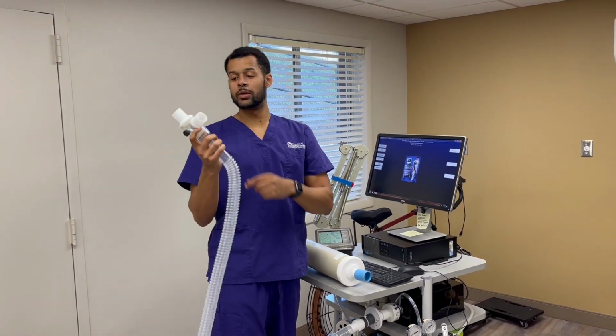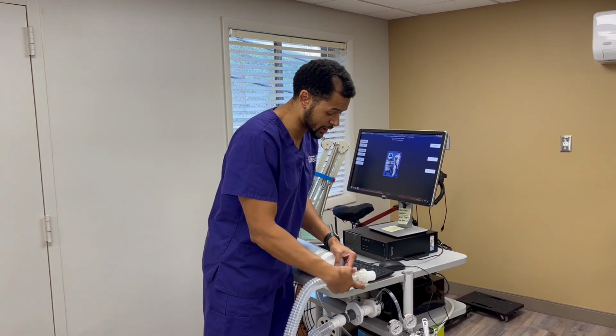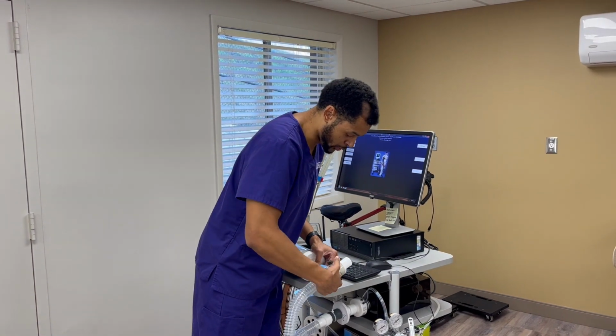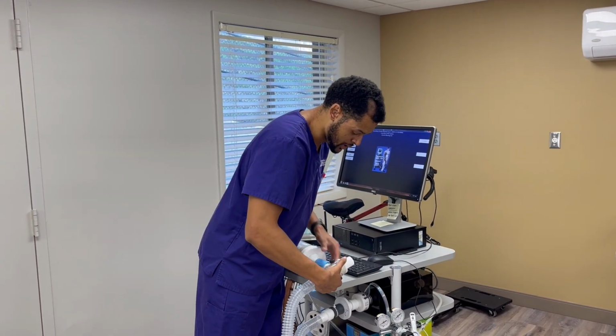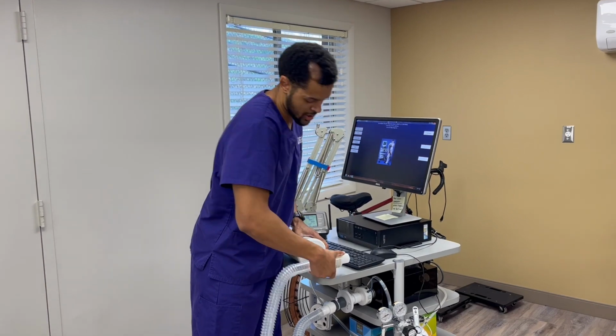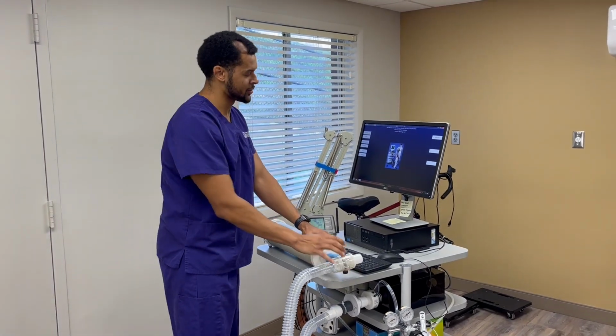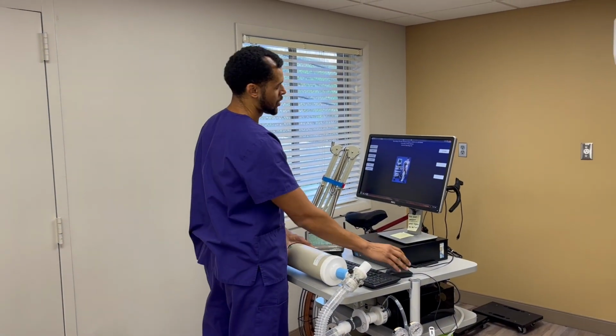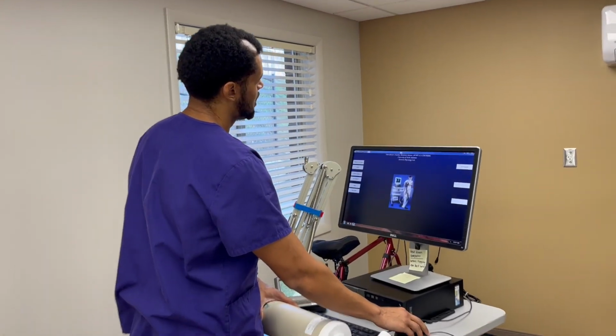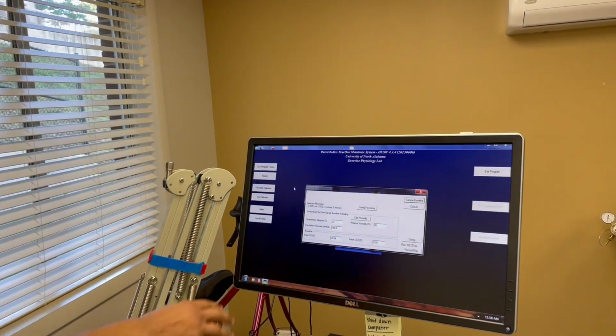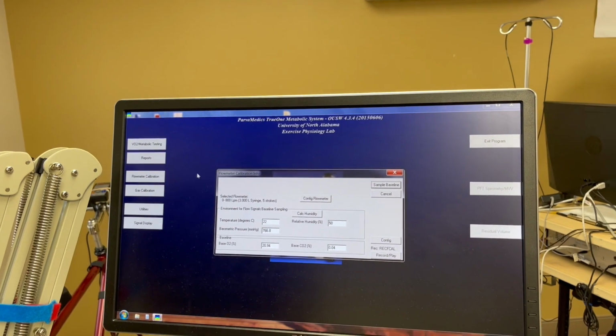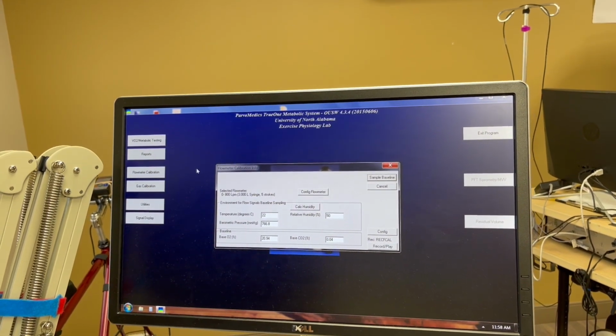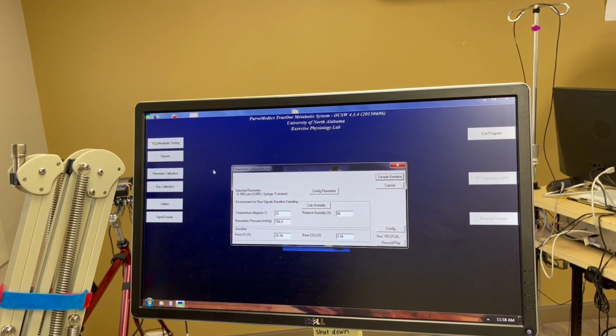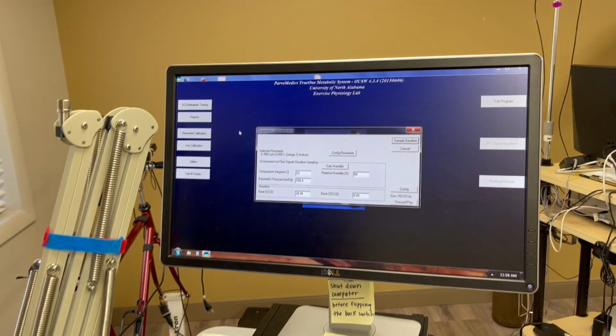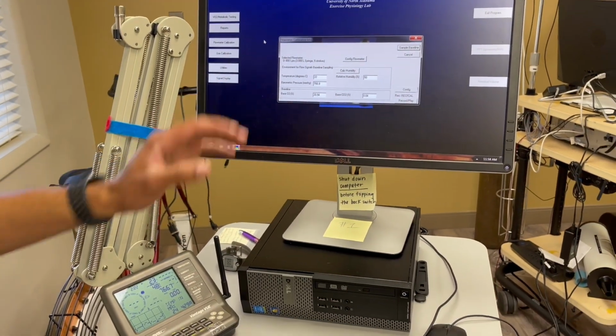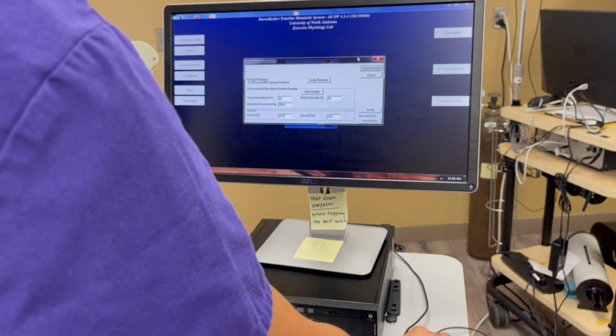Next, you're going to take the calibration piece and plug that into your 3-liter syringe. This is a 3-liter syringe because it mimics the lungs and normal breathing patterns. So next you're going to go onto the computer itself and click on the flow meter calibration found right here. Once you do that, this menu will pop up. You'll again check your room data. Right here it is still the same, so we're just going to hit sample baseline.